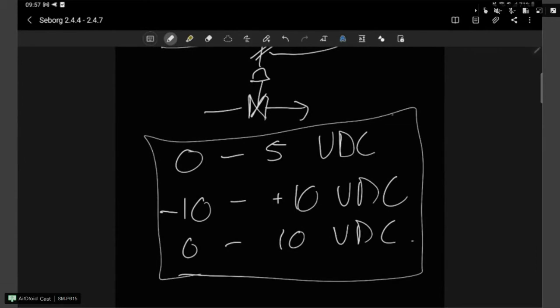The only problem with volts, and this is a question I like in CPB, is that with a voltage signal you've got voltage drop over lengths of wire. As a wire gets longer, the resistance goes up and the voltage drops because of that resistance, whereas the milliamp signal stays relatively constant.